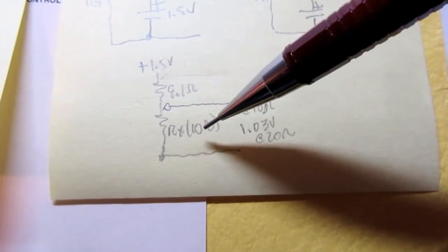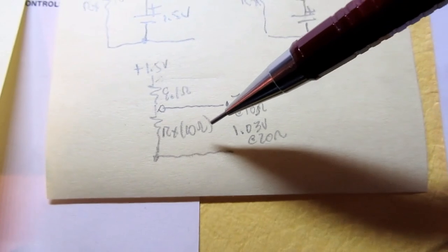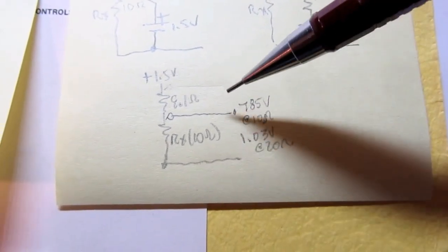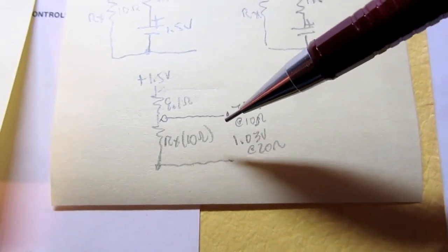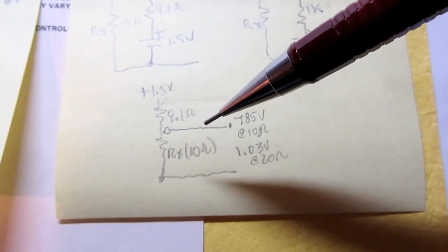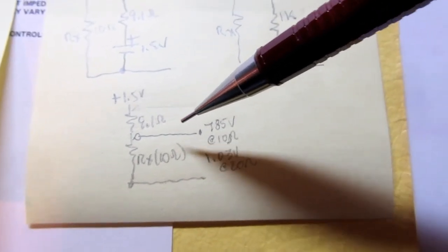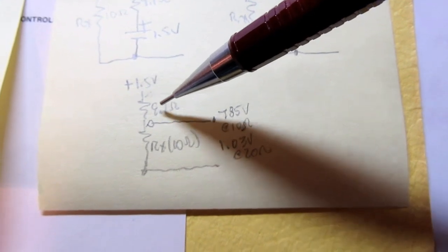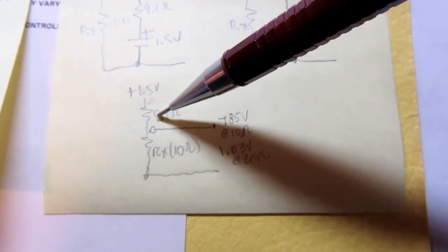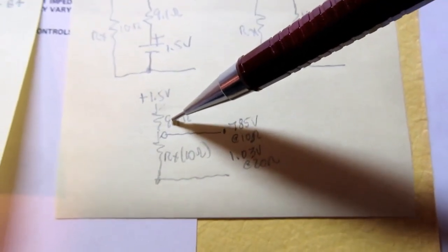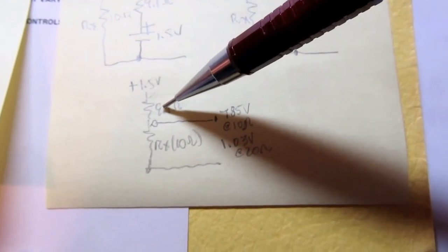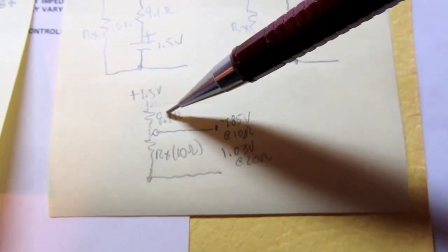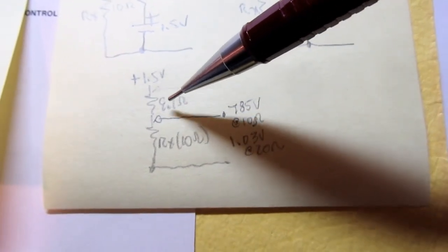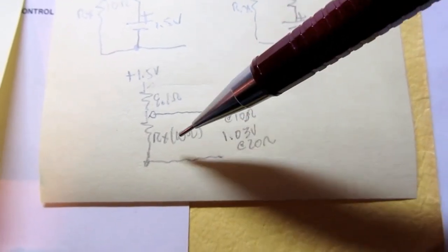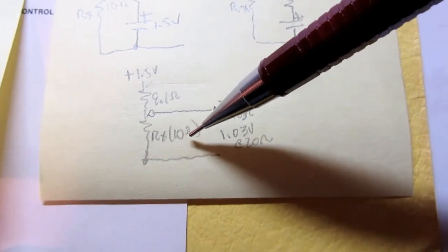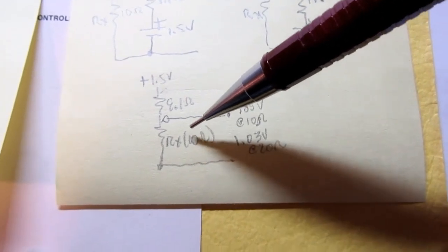In the times 1 mode, a 10 ohm resistor will give you a mid-scale reading, because that's where the scale is calibrated for a reading of 10. If you are in the times 100 range, then this resistor here gets another resistor added to it by the range switch, and it ends up being just a little bit under 1 kilo ohm.